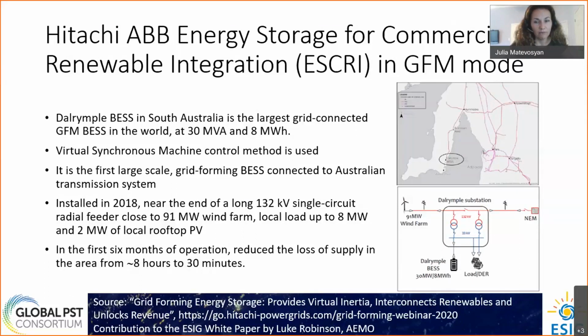So they have other applications. One of them is also by Hitachi ABB, where a same size battery is powering up a coal mine, but this is a microgrid application, whereas this one is actually connected with the Australian transmission system. It was installed in 2018 near the end of a long 132 kV single circuit radial feeder, and it's close to a 91 megawatt wind farm. It also has local load connected at the substation with a peak load of 8 megawatts. There is also 2 megawatt of local rooftop PV connecting into that substation.